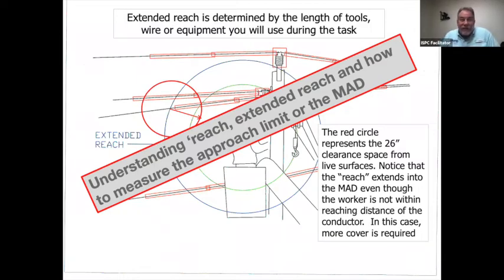Minimum approach distance: understanding the reach, the extended reach, and how to measure the approach limit. So basically what we're talking about here is your communication guy might be on a ladder next to a pole, and if he can physically reach up and touch that system neutral, then he is in the minimum approach distance.